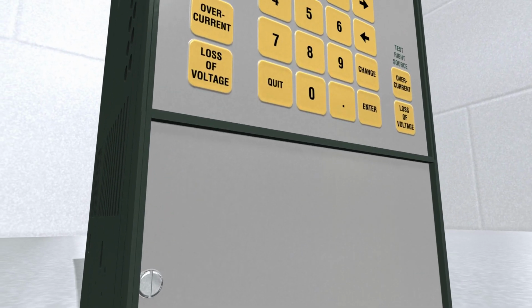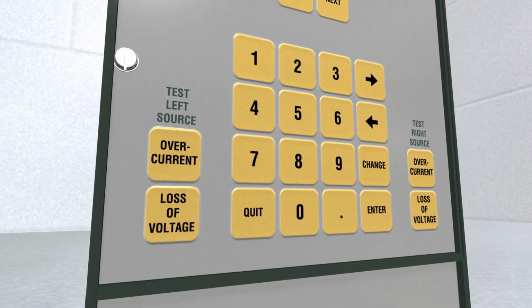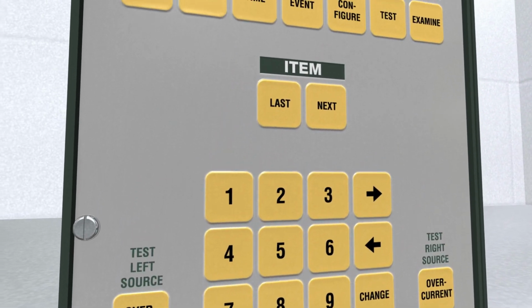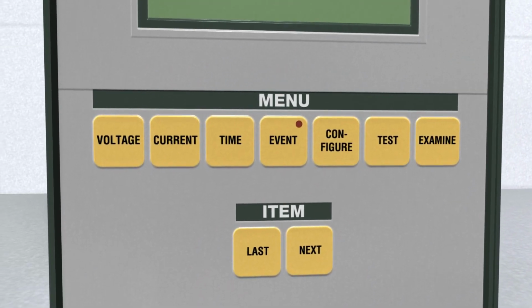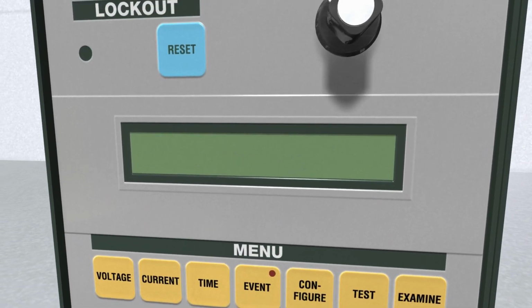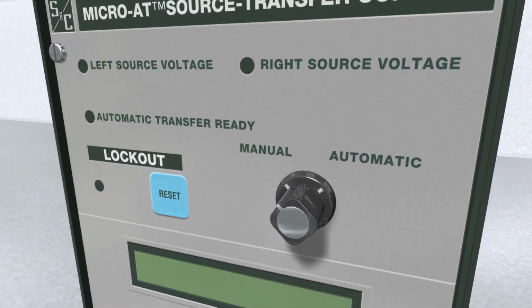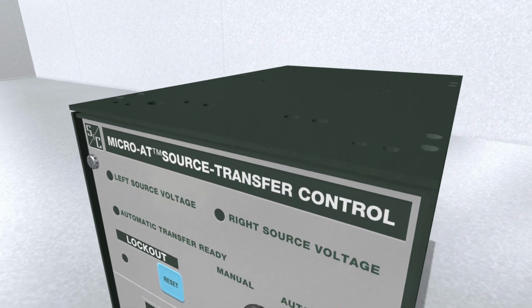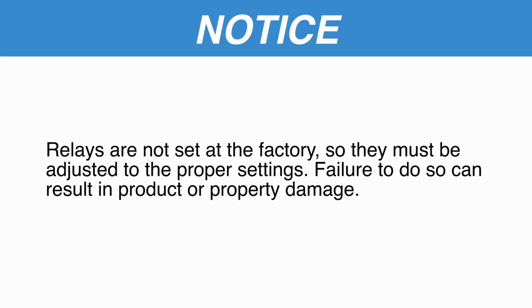Step 12. Remove all restraining tape and blocking from the movable elements of the meters and relays, if included, used to prevent movements of these parts during shipment, and check the elements for freedom of movement. Note: relays are not set at the factory, so they must be adjusted to the proper settings. Failure to do so can result in product or property damage.